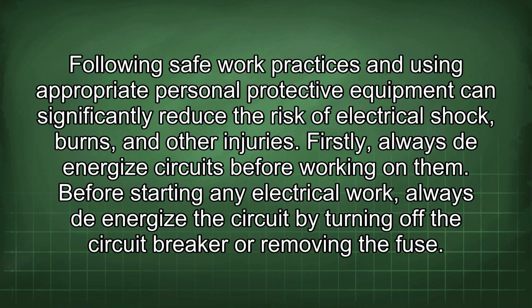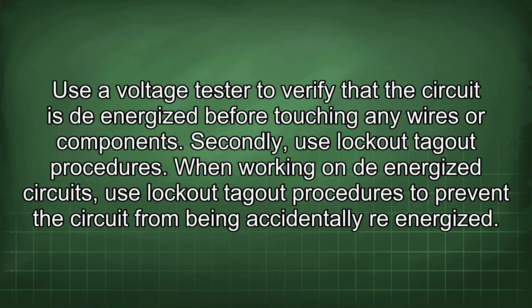Following safe work practices and using appropriate personal protective equipment can significantly reduce the risk of electrical shock, burns, and other injuries. Firstly, always de-energize circuits before working on them. Before starting any electrical work, always de-energize the circuit by turning off the circuit breaker or removing the fuse. Use a voltage tester to verify that the circuit is de-energized before touching any wires or components.